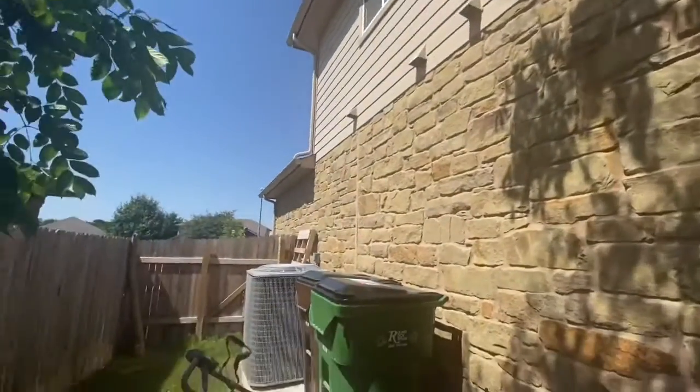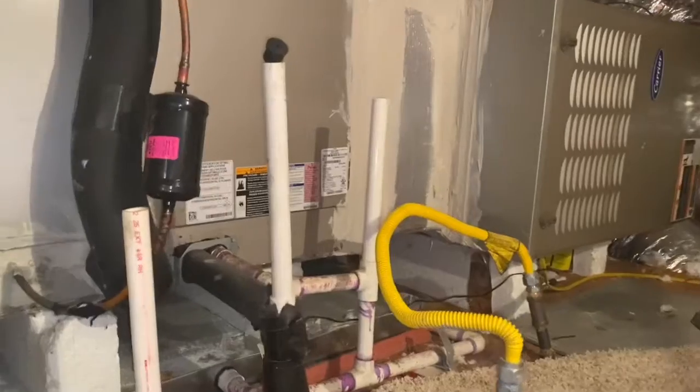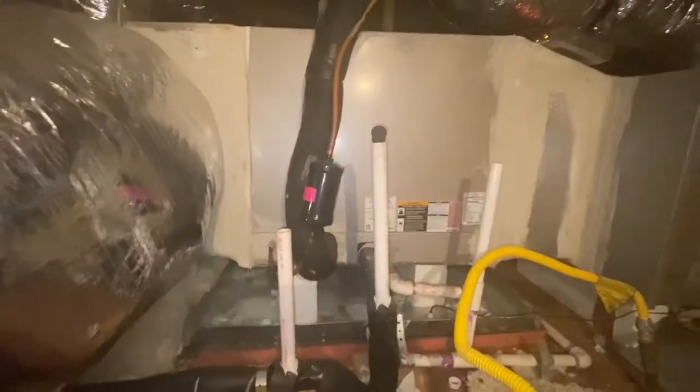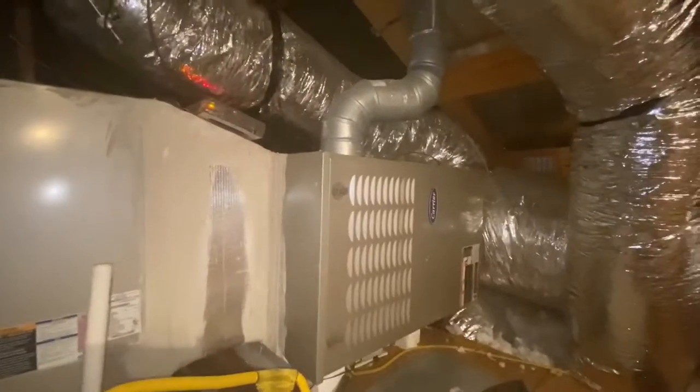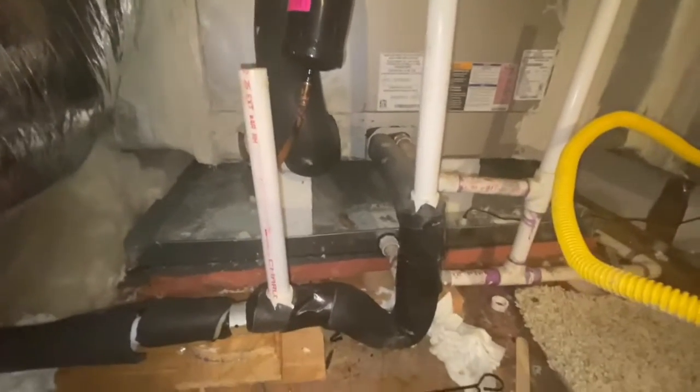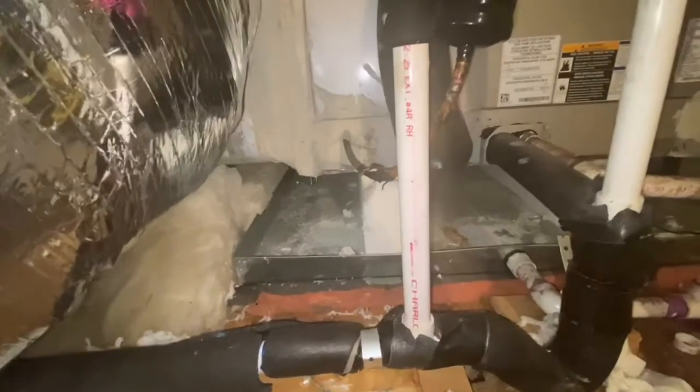And by the way, here is my AC unit, and let's go inside and check how this AC unit works and how the overflow occurs. If you're looking at my screen here, this is my Carrier AC unit, and I see this pan down here. This is the overflow collection pan. The most important thing is, whenever you see the overflow happening outside, come here and make sure that there is nothing in the collection pan. If there is water in the collection pan, that's a bad thing. You've got to work on it immediately.